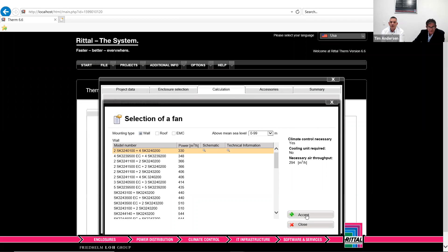Now, when we talk about using fans, we've also got to look at IP ratings on the design table, okay? Now, Rittal's fans are designed to draw over face, and you might be doing the engineering of a box that holds a million dollars worth of equipment in it. The concept is fans draw over face because we want to pressurize the cabinet to a degree and then use natural convection for the heat to dissipate out the top of the enclosure.